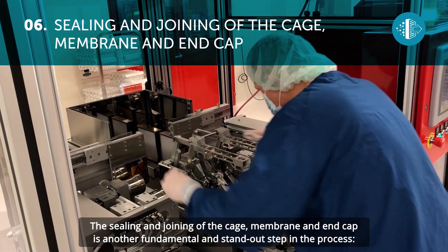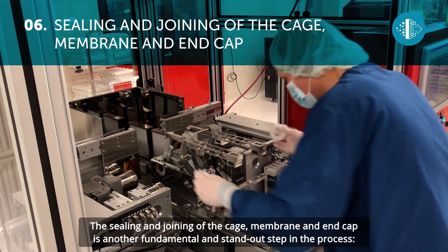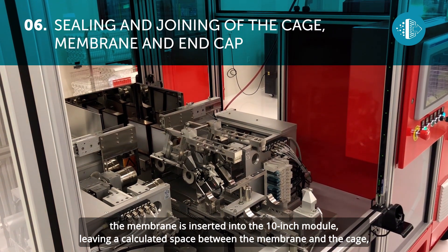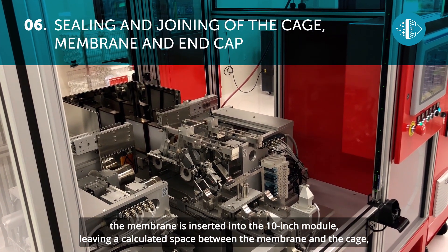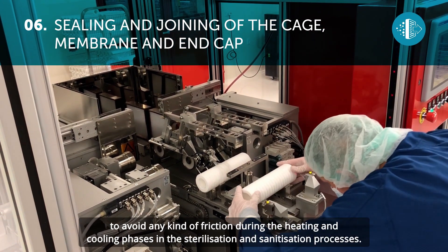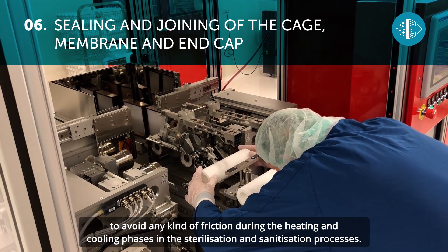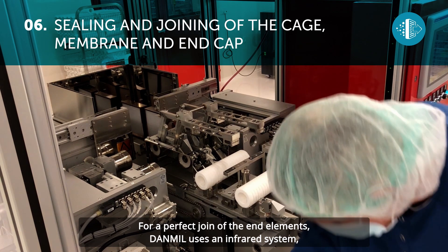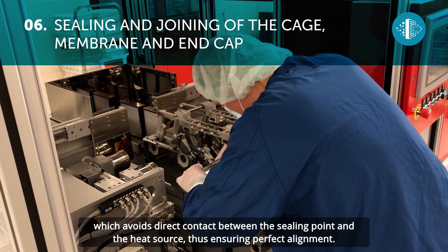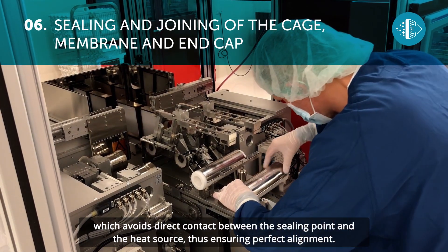The sealing and joining of the cage, membrane and end cap is another fundamental and standout step in the process. The membrane is inserted into the 10-inch module, leaving a calculated space between the membrane and the cage, to avoid any kind of friction during the heating and cooling phases in the sterilization and sanitization processes. For a perfect join of the end elements, DANMIL uses an infrared system, which avoids direct contact between the sealing point and the heat source, thus ensuring perfect alignment.